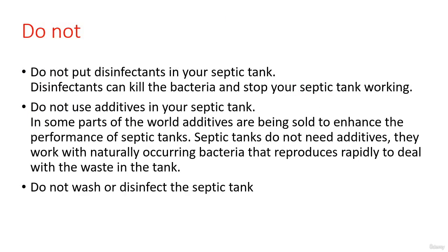Now let's check the do-nots. A very important thing: do not put disinfectants in your septic tank. Because in the septic tank we have the proliferation of good anaerobic bacteria that are responsible for the anaerobic process and lowering BOD levels. We don't want to kill this good bacteria. If you add disinfectants to your septic tank, this might kill these good bacteria and stop your septic tank from working, killing the biological process within the septic tank.